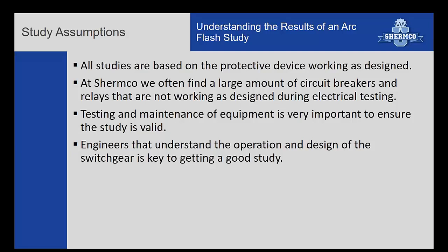As I discussed, you can't say this piece of gear is a Cat 4 gear. It's a Category 4 at some distance. I see a lot on panel boards where electricians are pulling in cable energized. Those calculations are typically done on panel boards at 18 inches. If they're pulling in cable and they're physically within 6-8 inches of the bus, the incident energy is much higher at 6 or 8 inches than the sticker shows at 18.